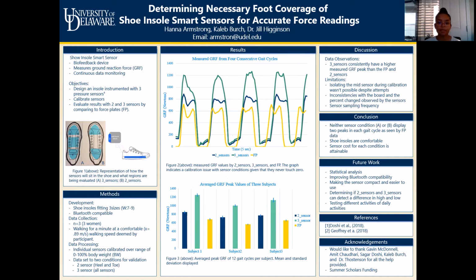It is apparent that both sensor conditions measured higher values than the golden standard force plates, this being in the graph, pun unintended, the color gold. In Figure 3, where the peak forces are being compared between each condition for 3 subjects, the pattern continues with each sensor set measuring higher and the 3 sensor set measuring the highest. These observations lead to the conclusion that further steps need to be made during the calibration stages to ensure that the measurements are not being exaggerated.